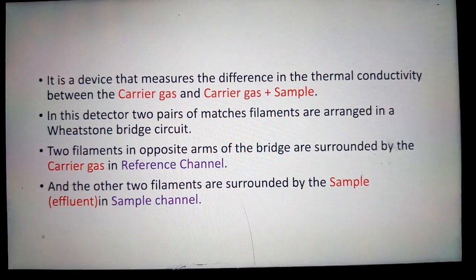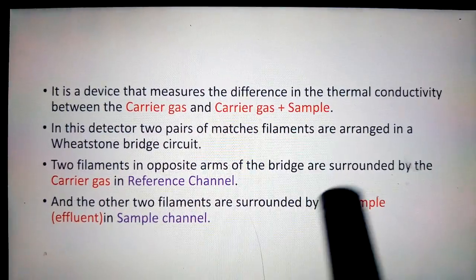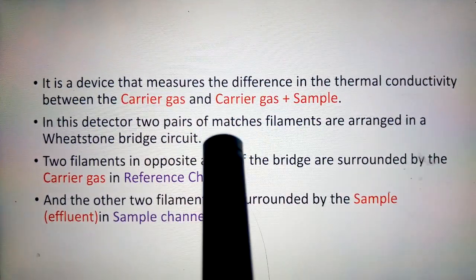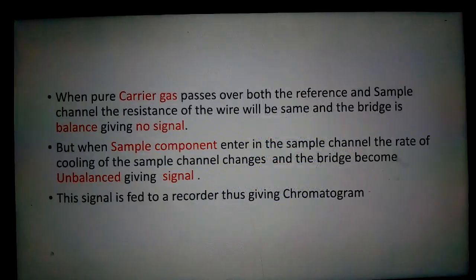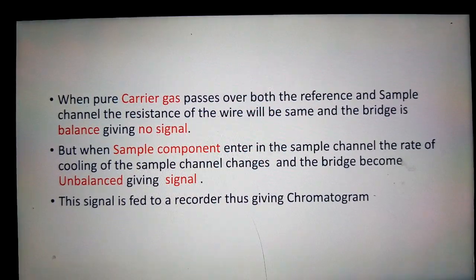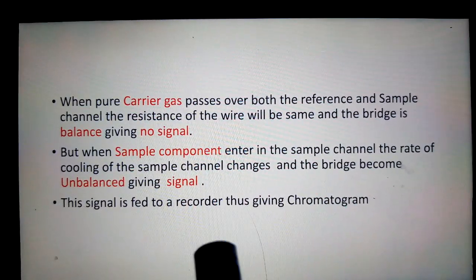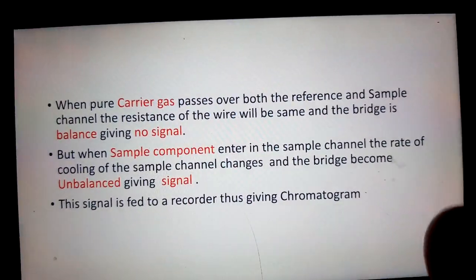To summarize: the TCD is the device that measures the difference in the thermal conductivity between carrier gas and carrier gas plus sample. There are 2 pairs of matched filaments situated in a Wheatstone bridge circuit, and there are 2 channels: reference channel and sample channel. When the carrier gas passes over the filament, the bridge becomes balanced and gives no signal. When the sample passes over the filament, the bridge becomes unbalanced and gives a signal, which is fed to the recorder to give a chromatogram.